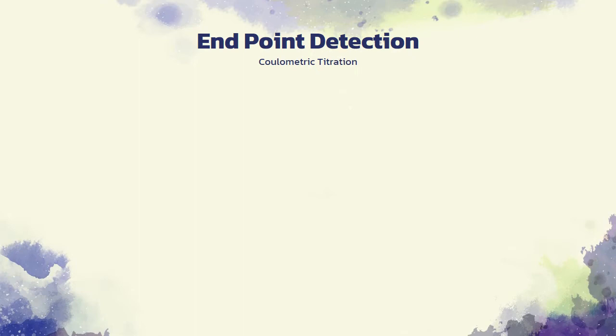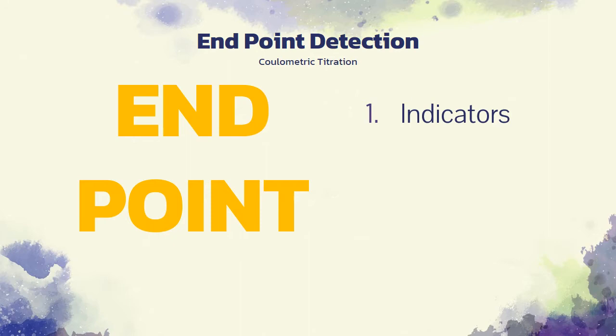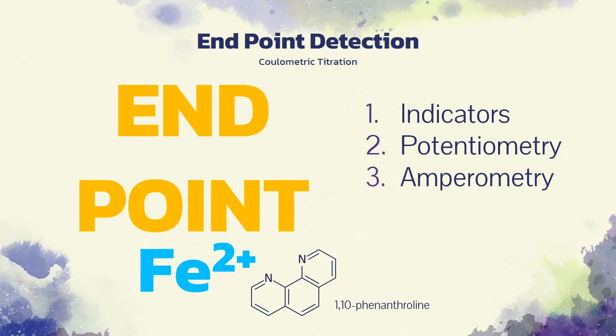Coulometric titrations, like their volumetric counterparts, require a means for determining when the reaction between analyte and reagent is complete. Generally, the endpoint indicators described in volumetric methods are applicable to coulometric titrations as well. For example in the titration of iron 2+, an oxidation reduction indicator such as 1,10-phenanthroline can be used. As an alternative, the endpoint can be determined potentiometrically or amperometrically. These are used in Karl Fischer titrators. Furthermore, some coulometric titrations utilize a photometric endpoint.